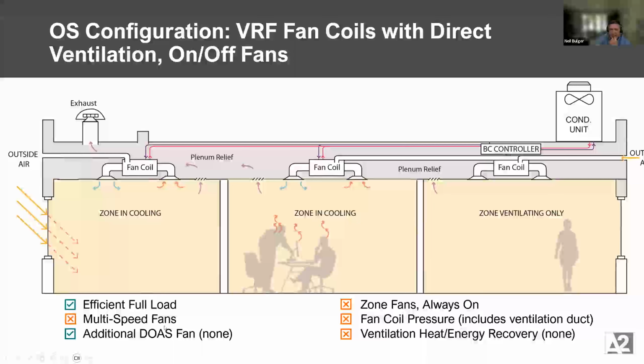I guess some benefits to this configuration is there's no additional DOAS fan, right? It's only that fan working. It has to pull the air through that duct, but it's a much, much smaller design. But we have the fans always have to run because they need to be there. The pathway, the fresh air makes it into the building. There's additional pressure drop I mentioned, and there's no heat recovery.